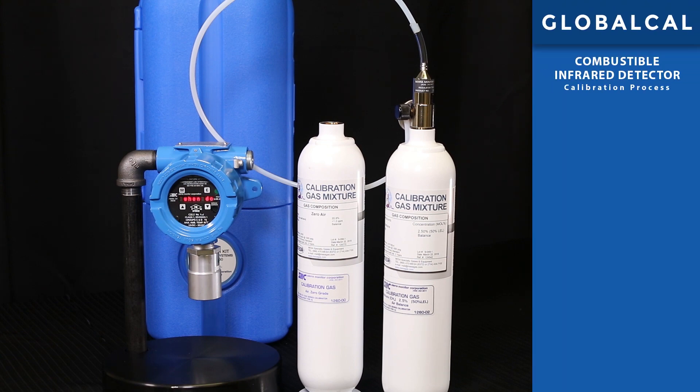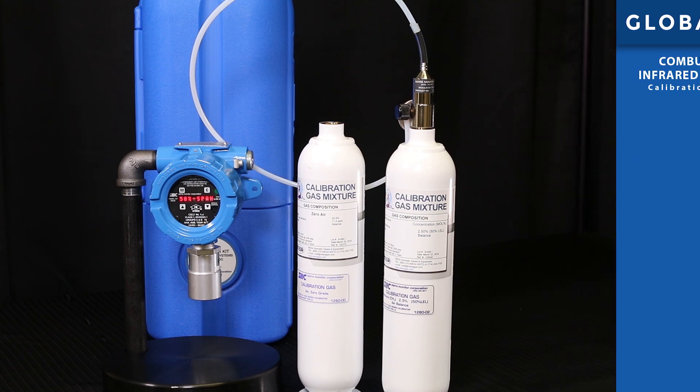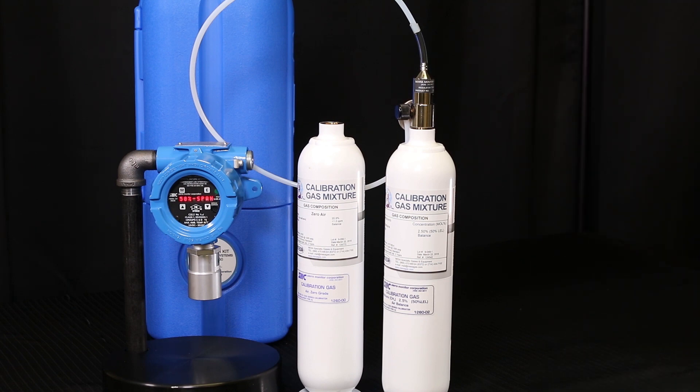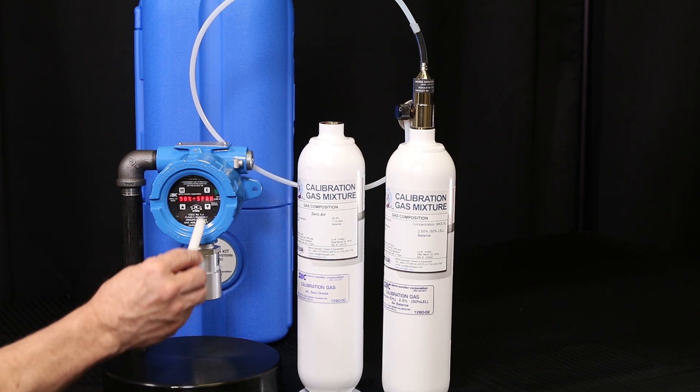Next is Step 2: applying the span gas. First, confirm the span gas concentration. Note that this is a combustible gas detector and we're using 50% LEL methane as our standard for this demonstration. Not all span gas concentrations are the same. Use the magnetic wand to tap E to confirm.